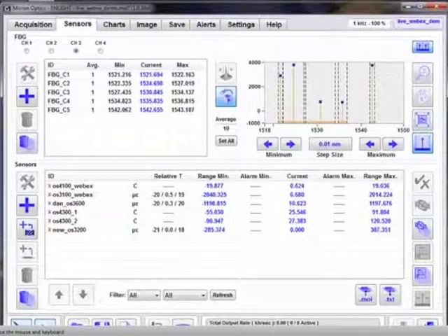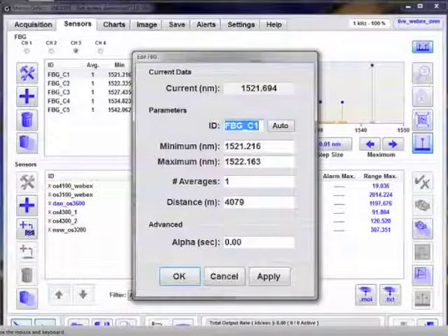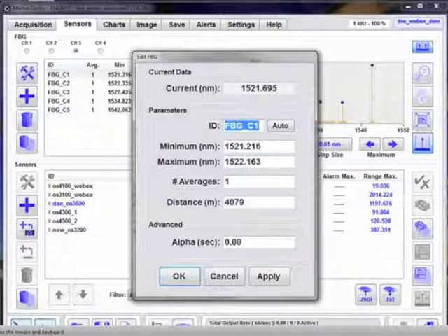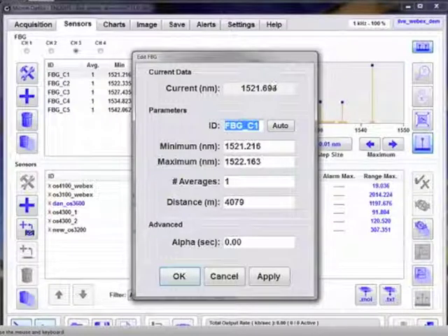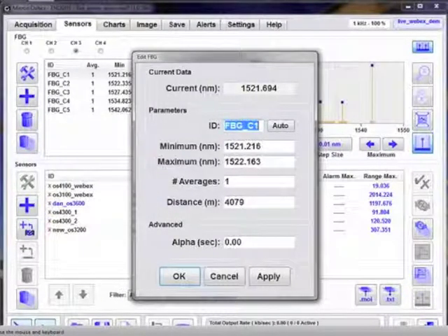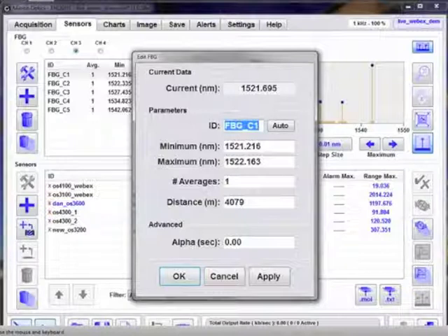So in ENLIGHT, yes, you can average on a per FBG basis. This is for both the SM125 and the SM130, after any spectral averaging that would be done from the acquisition tab. So if you're averaging the value of that FBG, then any expressions that reference that FBG value will be acting upon that averaged value. This is commonly used for temperature sensors or temperature compensation sensors, where you don't expect appreciable changes or very fast dynamic changes, and averaging directly improves the repeatability of the compensated sensor by eliminating any data acquisition noise on that particular sensor.